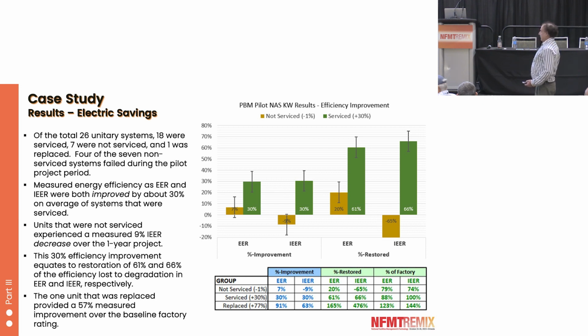So we measured the energy efficiency as both EER, energy efficiency ratio, and calculated IEER, so we could compare it to the factory rating. And those were both improved by about 30% on average among the 18 units that were serviced. I don't have the chart here that shows how much each unit was improved, but there's quite a range. I mean, there's some units that were 50 or 60% improvement. There's some units that were only 5% improvement. And we saw the same thing at the other 3 sites that we did.